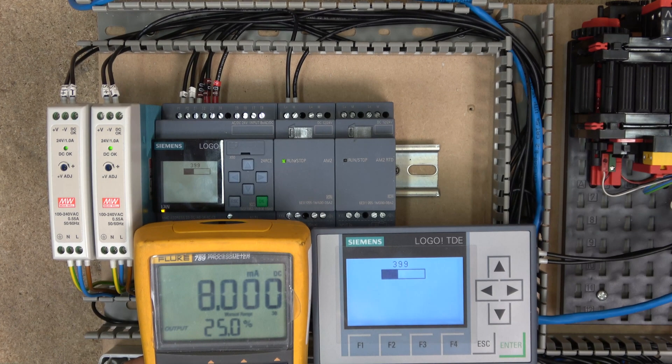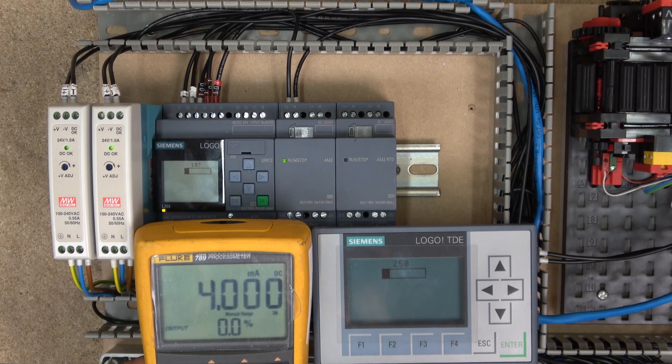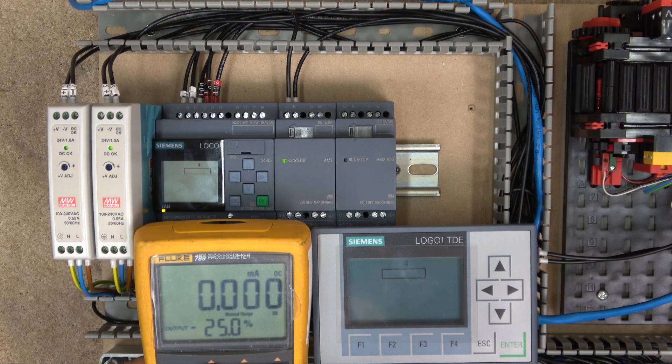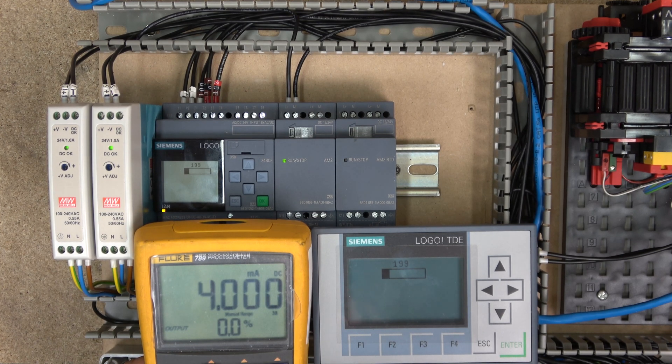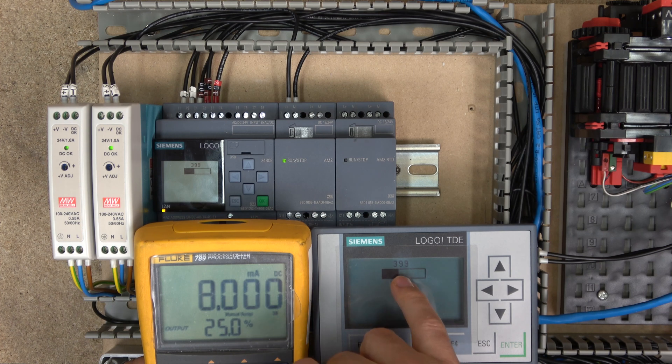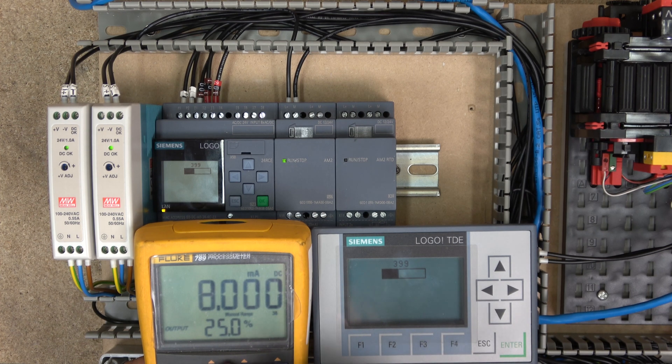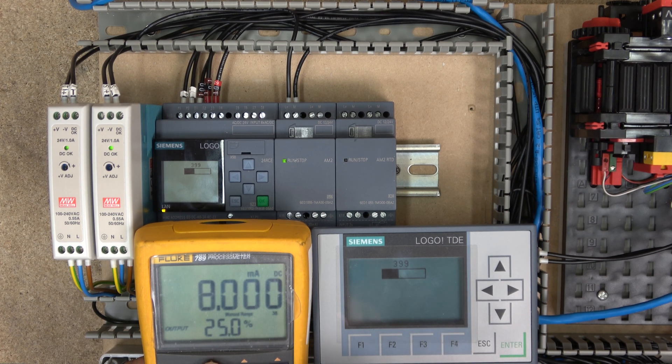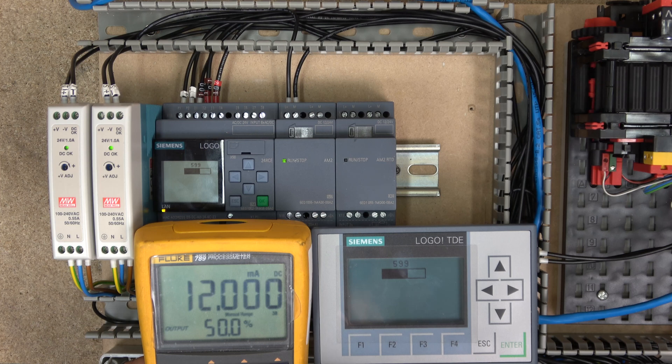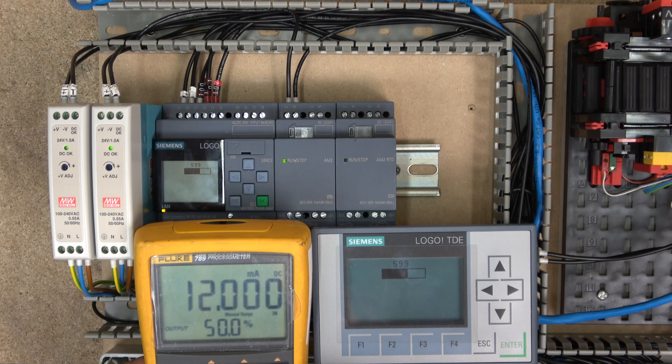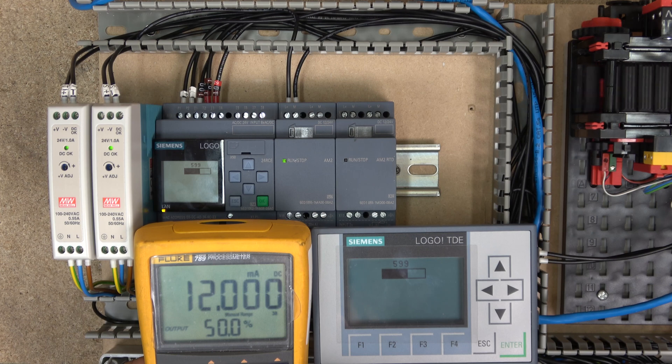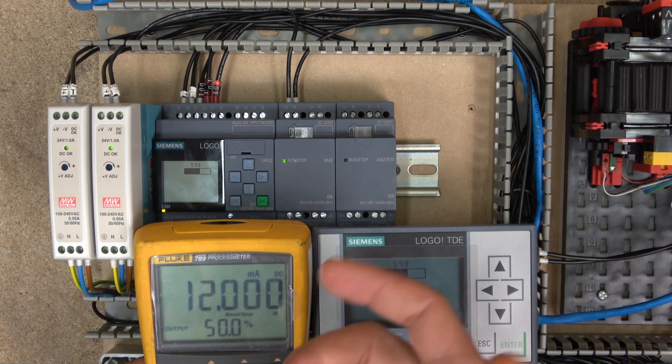Here we are. So as you've already seen it before, here we go. So when I move around, you can see the values are changing as milliamps goes up. You could put that like a tank full and things like that. As you can see, as I go up to 600, because it's gone past 500, it turns on the conveyor belt and it runs the conveyor belt.